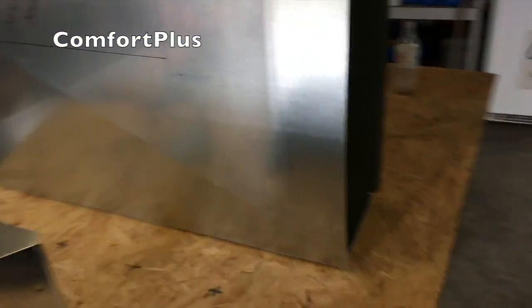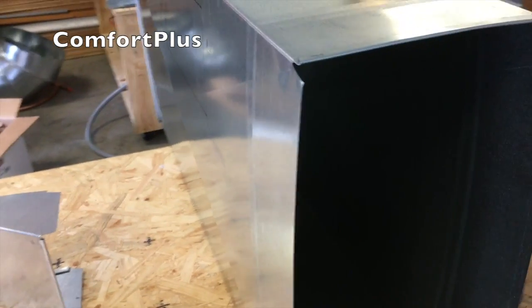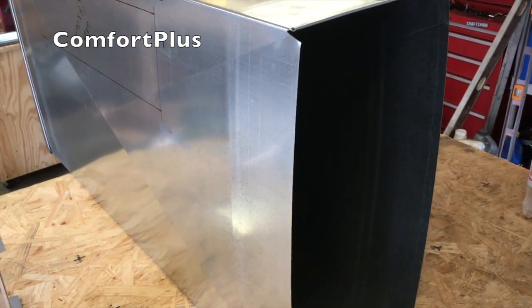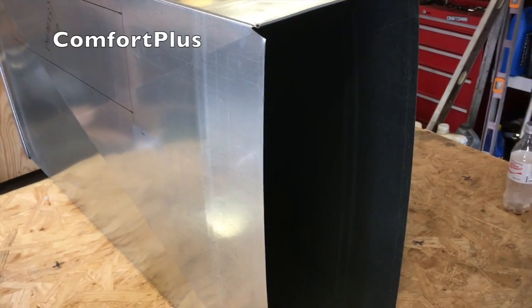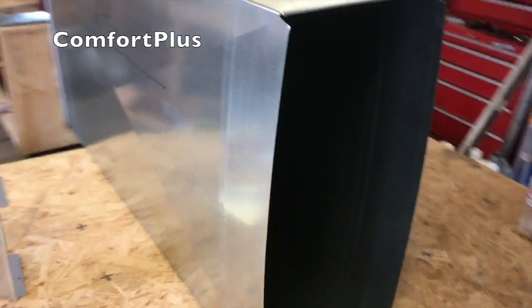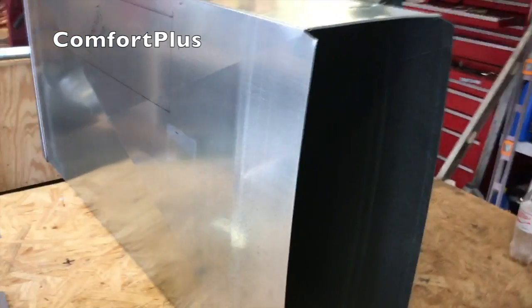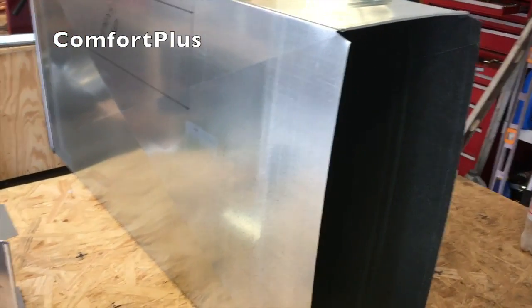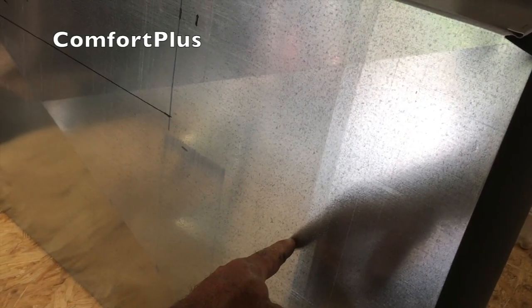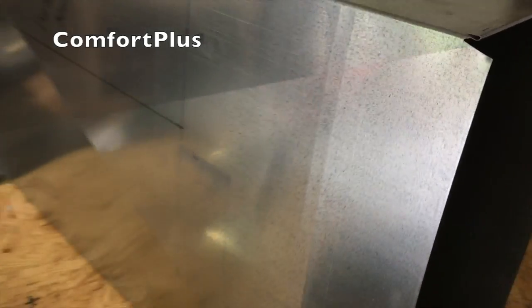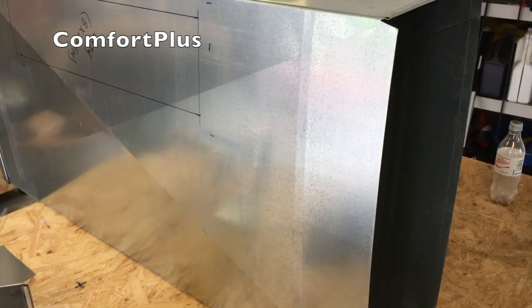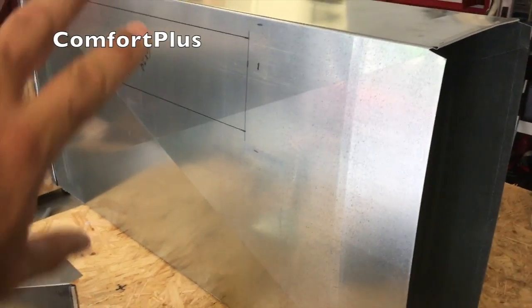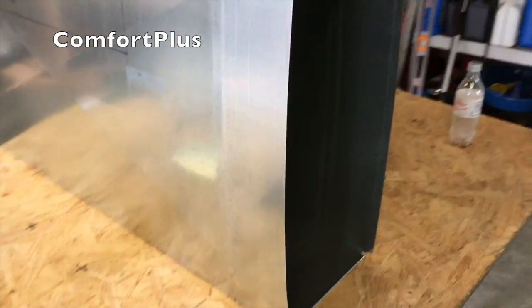Then what will be left is to adapt this 10 by 24 duct to that 11 by almost 20 coming off the air handler. I'll build a transition piece. It'll probably be a couple of feet long. I'll look and see. I've got to put a discharge air temperature sensor in this duct for the zone control, so I'll make sure how far they want that from the branch ducts and also the fan, but I'll build a transition piece here.